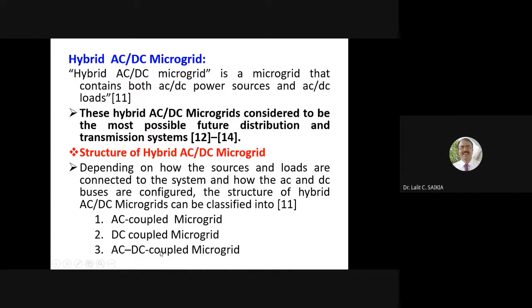In an AC coupled microgrid, all sources - DC DG, AC DG, energy storage - are connected to one AC bus. AC load is directly supplied from this AC bus, and if there is some DC load, it can be supplied via a power electronic converter, an AC to DC rectifier. When grid connected, the AC bus can be directly connected to the utility grid. This structure is commonly used when the dominant generation sources in the microgrid produce grid level voltage directly, such as from a diesel generator, so there may be a diesel generator here.